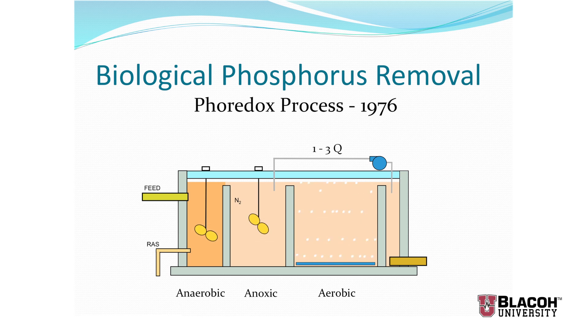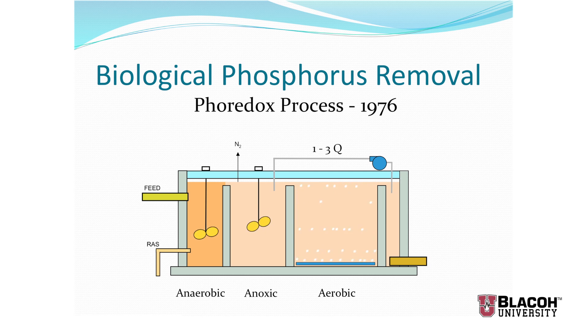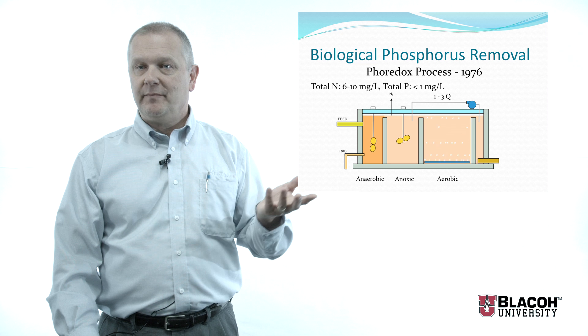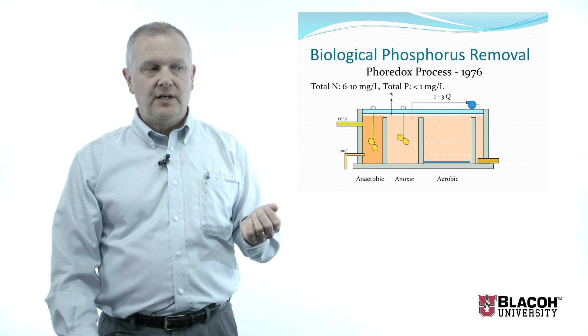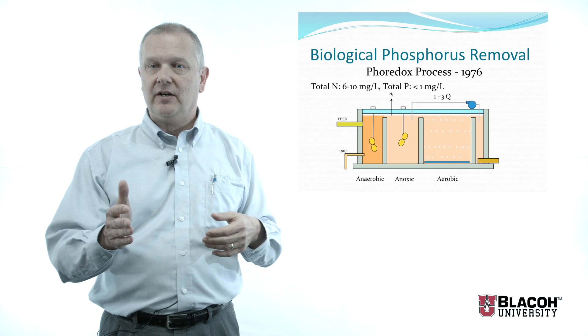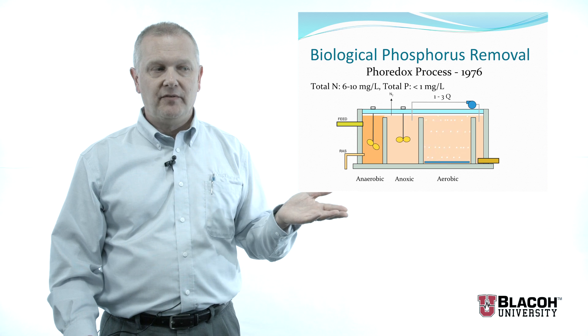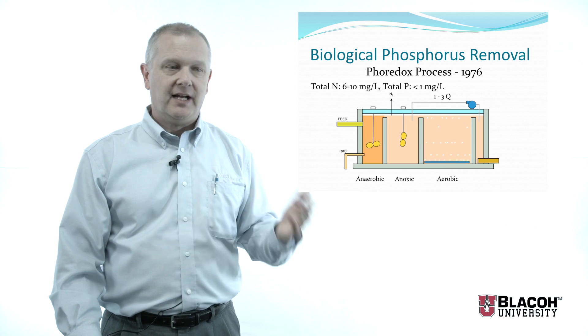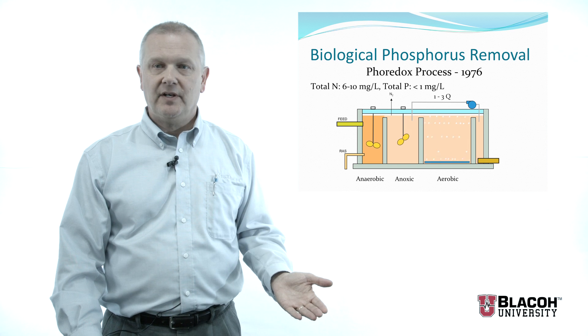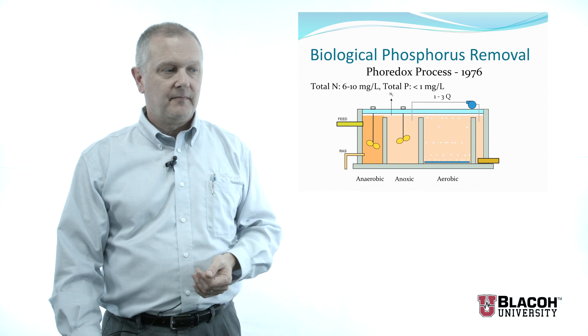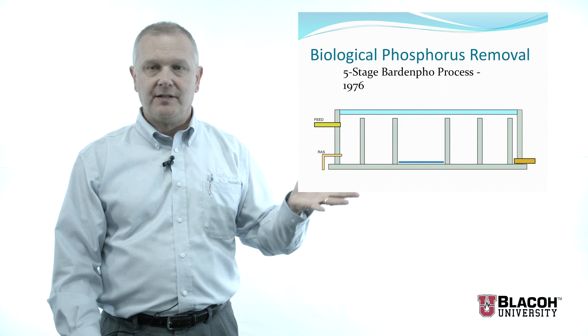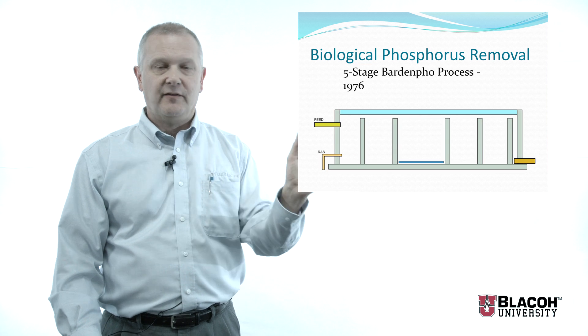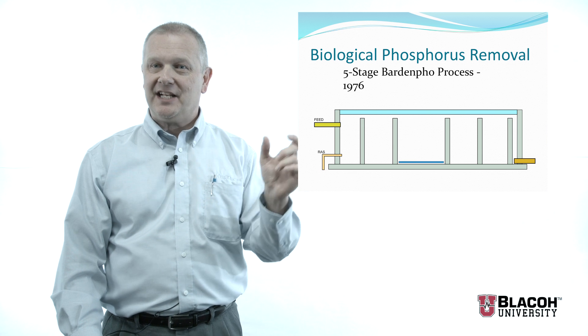This process can reduce nitrogen to about 5 to 10 milligrams per liter and reduce total phosphorus down to about one milligram per liter or less. So if a plant has a limit of one milligram per liter, they can reliably remove phosphorus biologically without buying any chemical or dealing with chemical sludge. We can also do this in the BARDENPHO process — in fact, the 'pho' in BARDENPHO actually stands for phosphorus, and it was originally designed as a five-stage system with the anaerobic phosphorus removal stage up front.